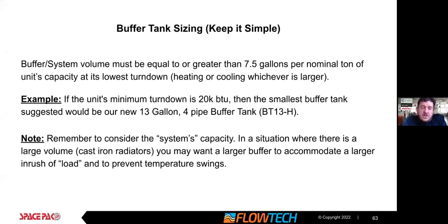One thing to note is system capacity will also impact the buffer sizing. So if you have a super high volume system and you need stored BTUs, high volume BTUs to be a fast response situation, that might impact it. But otherwise, we can get away with a little bit smaller of a buffer tank, which is very helpful for tight spaces and whatnot.